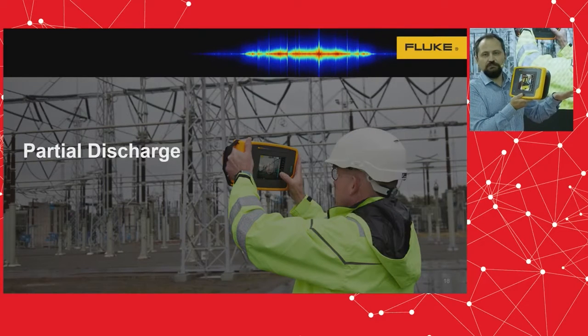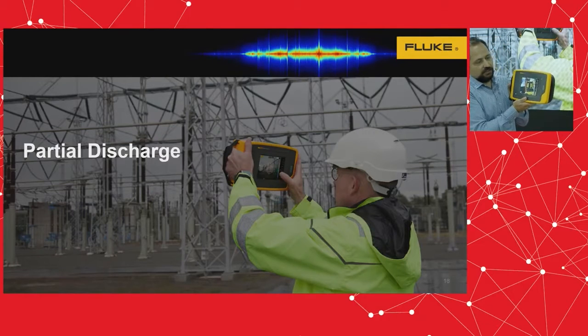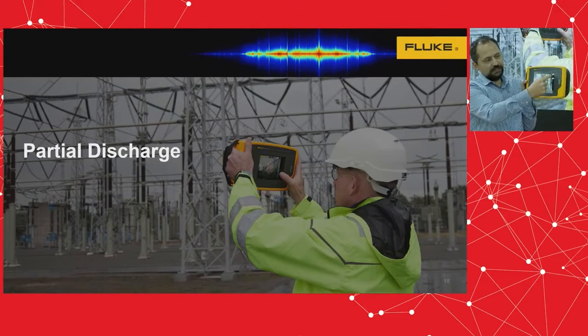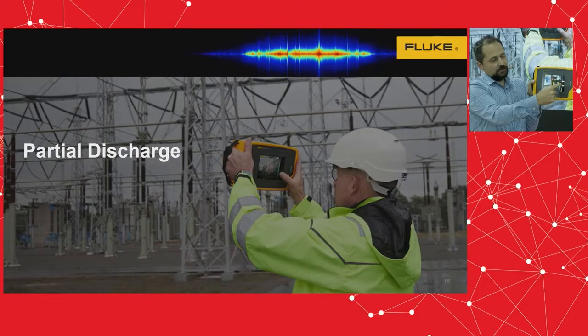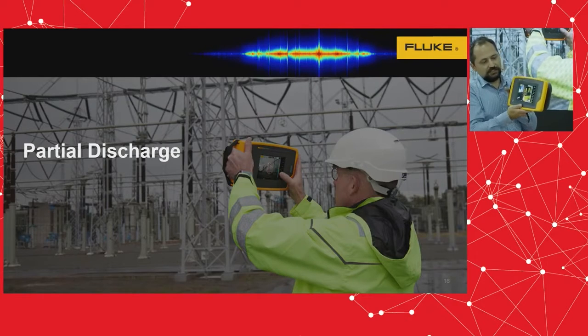Of course, there is no compressor system here, no gas system that I can show you. But what I have done is generate a 20 kilohertz sine frequency, a pure tone, with my cell phone that is over there. So the only thing I need to do is go here to the frequency spectrum and get this square that you see here. This is like a filter. Actually, it's a filter. You just move it down just to cover the area where you see that there are spikes, which is around the 20 kilohertz band.